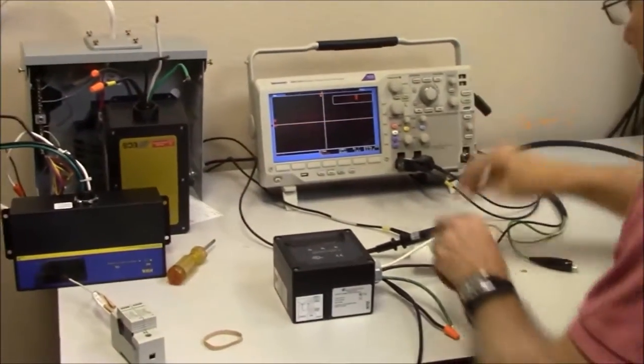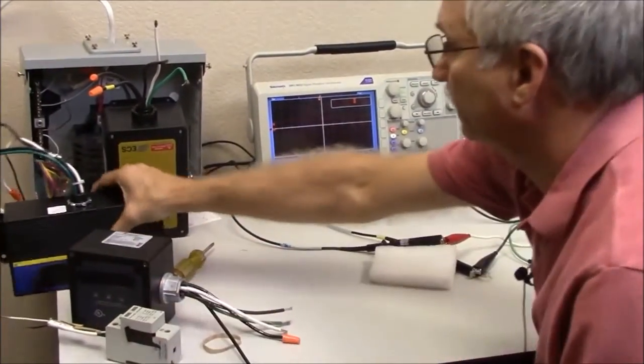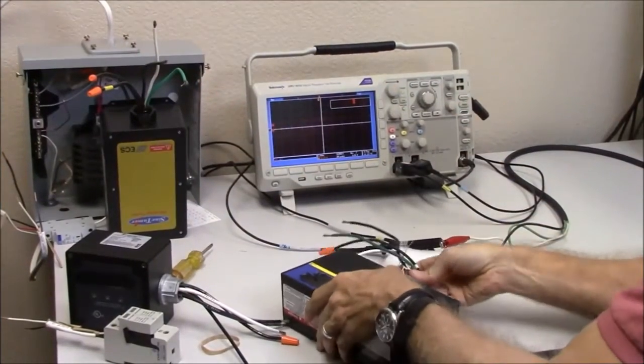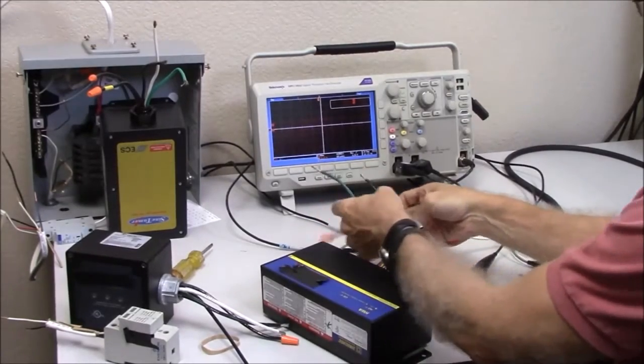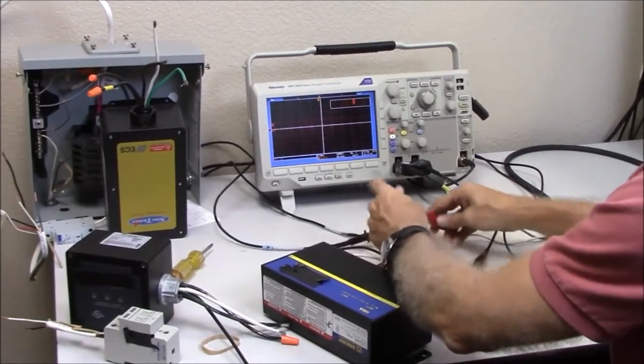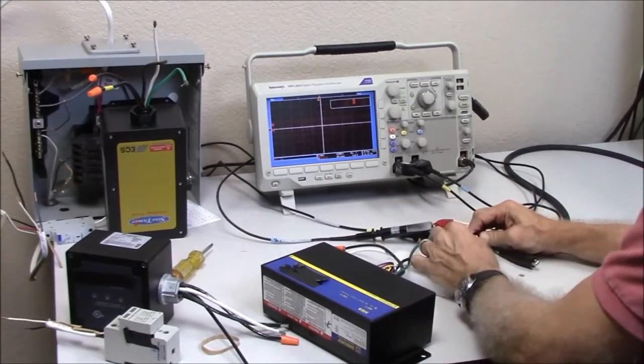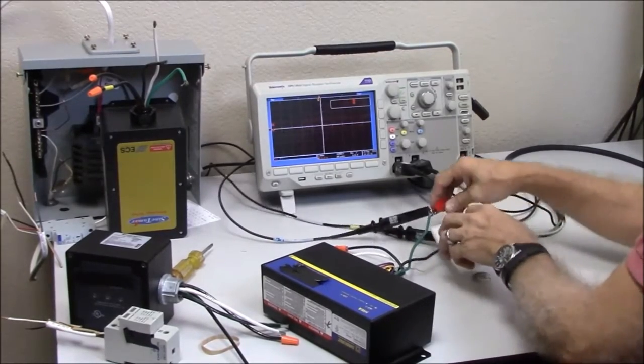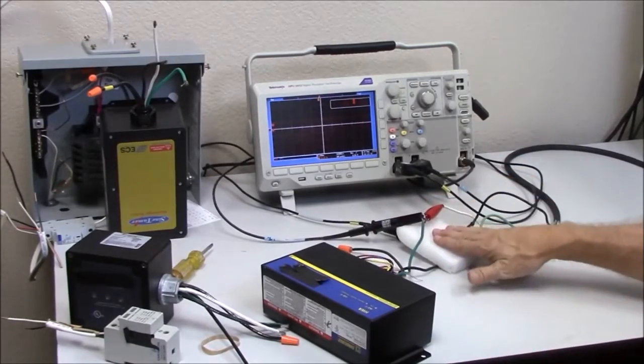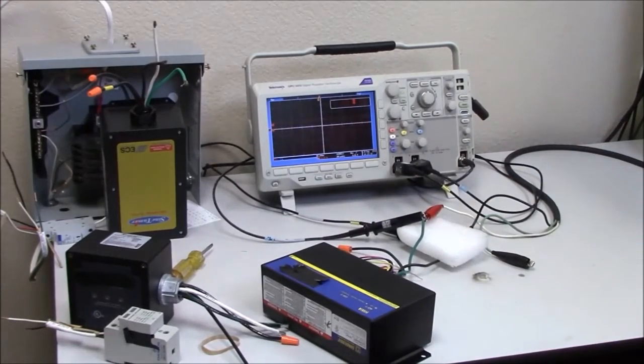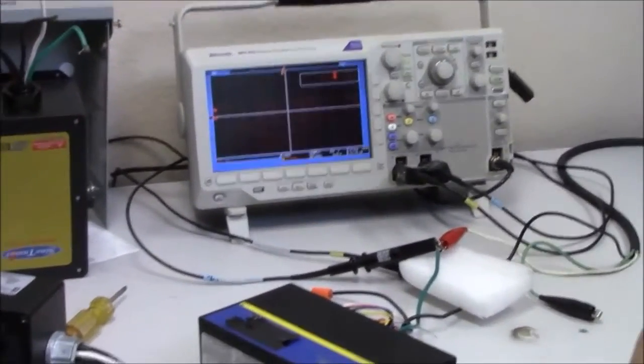Okay, let's clear that, we'll remove this unit and set it aside. This unit here is quite popular. It can be mounted internally into a panel itself or externally, and this unit actually has an audible alarm that will signal when there are problems within the unit or when the dry relay contacts are not connected. So we're going to test this one line to ground as opposed to line to neutral. We'll apply power, LED is on, then charge up the generator.